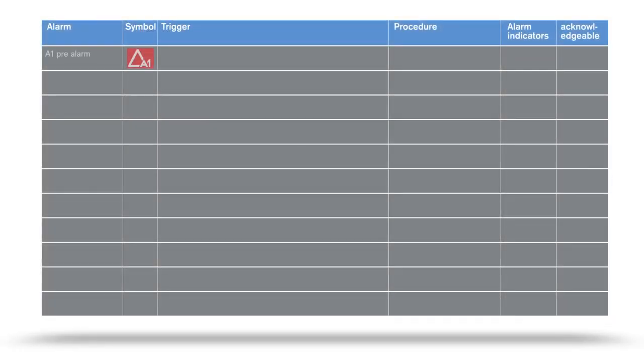The A1 pre-alarm sounds when the concentration is higher than the set threshold value. There is not yet acute danger. This alarm can be acknowledged by pressing the green OK button.